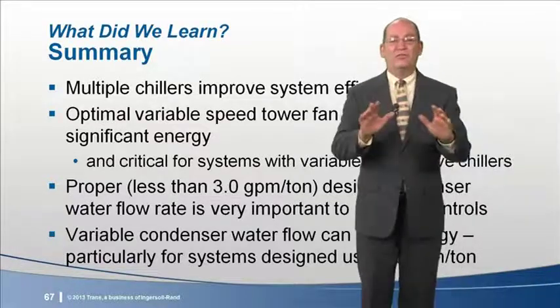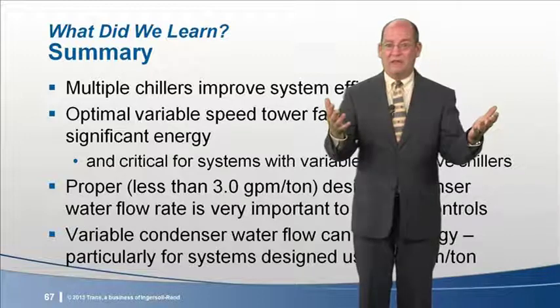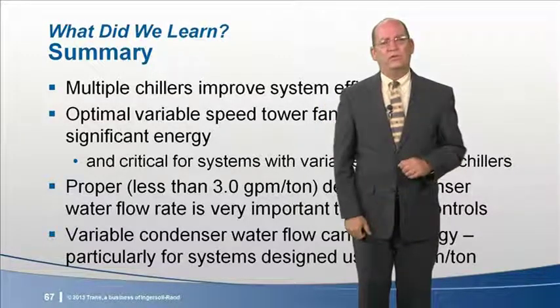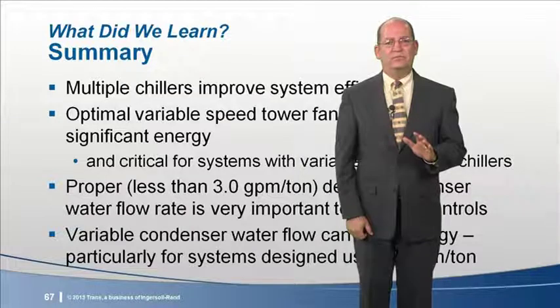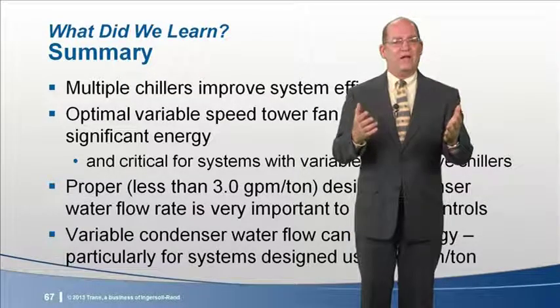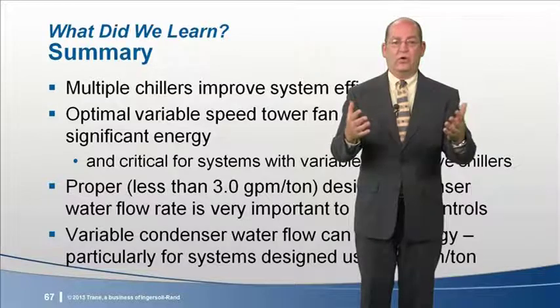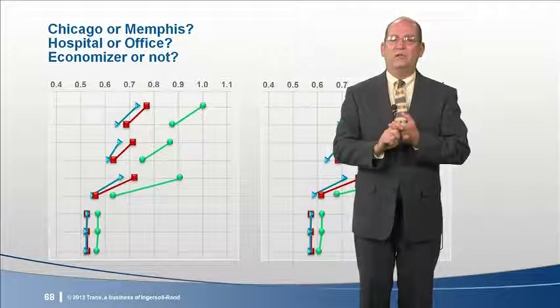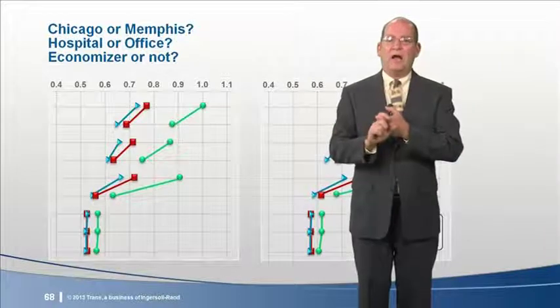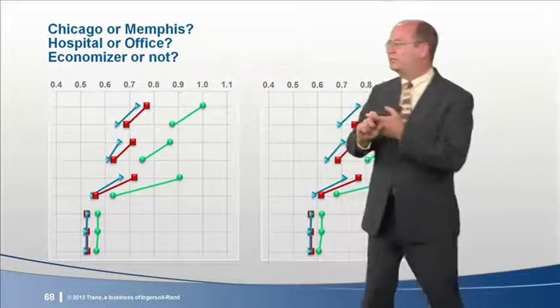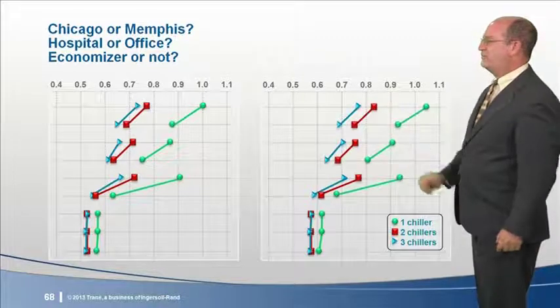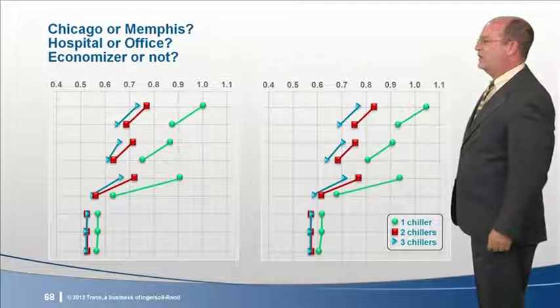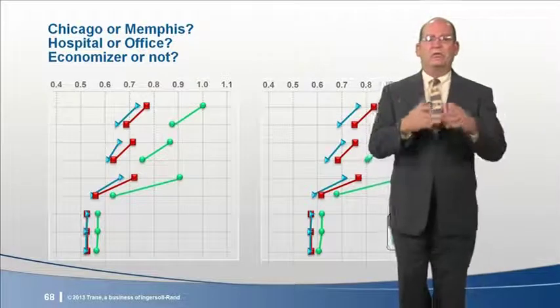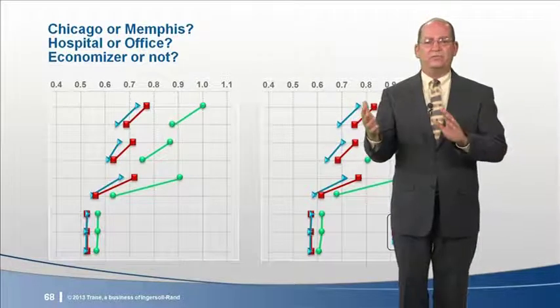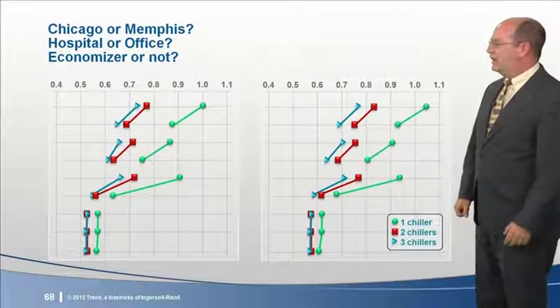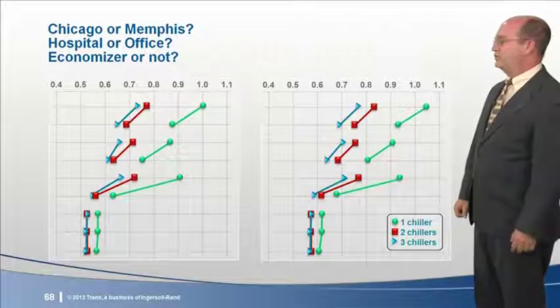So, this is for an office building in Chicago with an economizer. Do similar conclusions hold in other climates for other building types? We don't have the time to examine every climate or building type, but let's look at a few more. First, a hospital without an economizer in a more hot and humid climate, in this case, Memphis. Here are the side-by-side comparisons of the two buildings and locations. While the actual performance in terms of annualized kW per ton is different, the similarity of the direction and proportion of changes is striking.